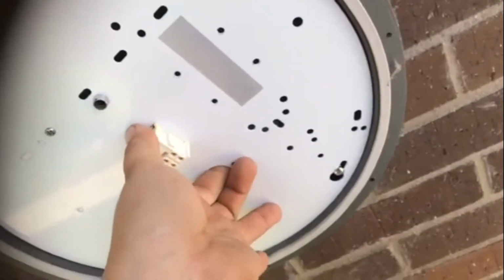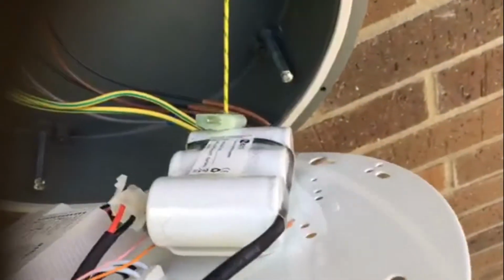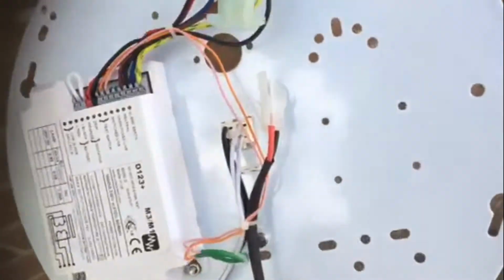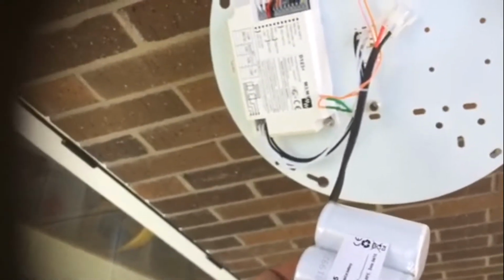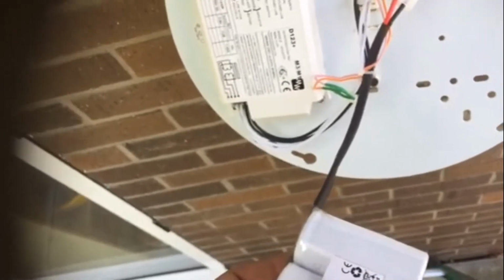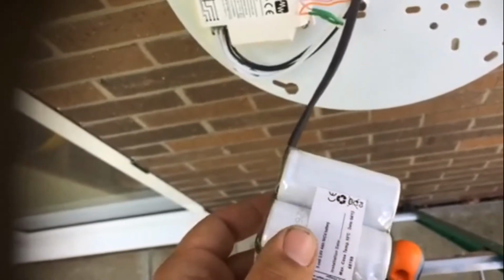Apparently this emergency light fitting failed in a 3 hour and an hour test. See what we got. Well, there's your problem. It's never been connected. And this extension was built in 2015. And this was a new light fitting in 2015. So, yep, changing it because I don't fancy putting this back in if it's fucked. It spent 2 years dead.